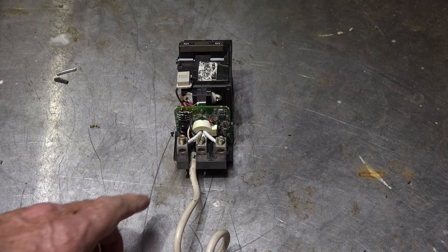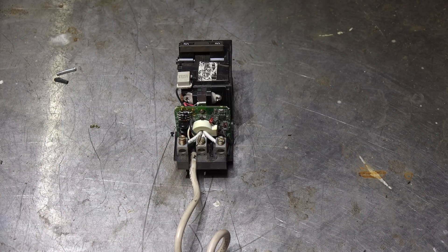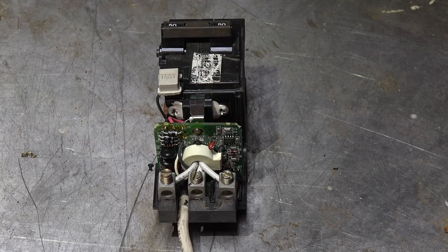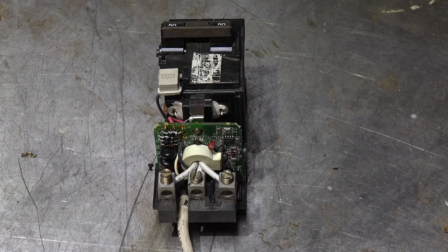I didn't really mention why it's there. There are three terminals here, and that one terminal in the center is a neutral — it goes through the inductor. But on some 240-volt appliances, part of the circuit is 120 volts. For example, with an electric dryer, you'd have 240 volts going between the two hot legs for the heating element...